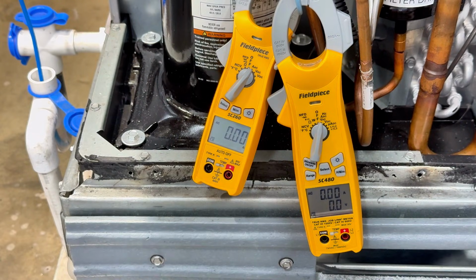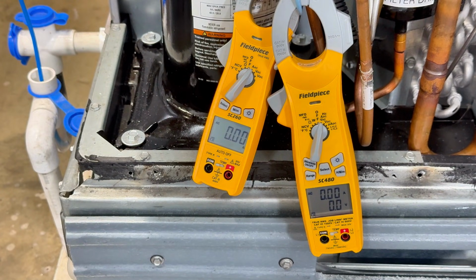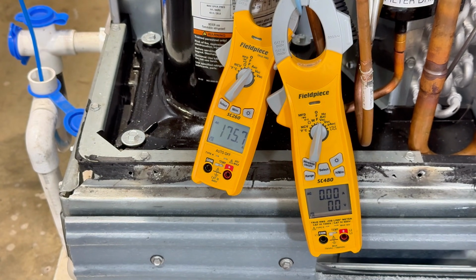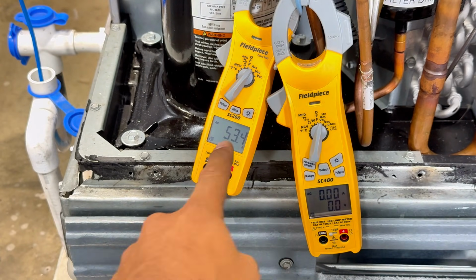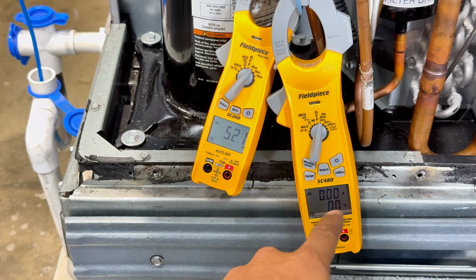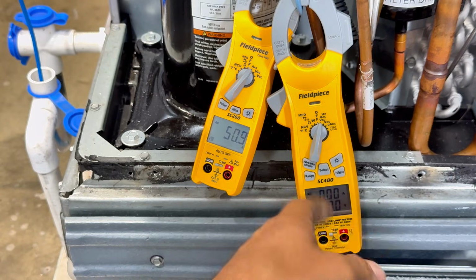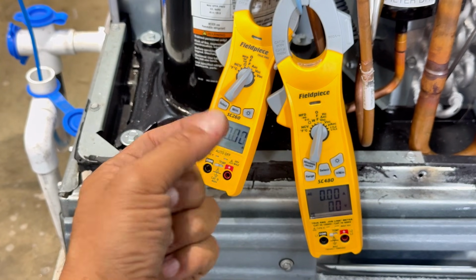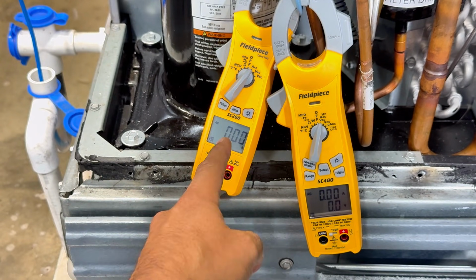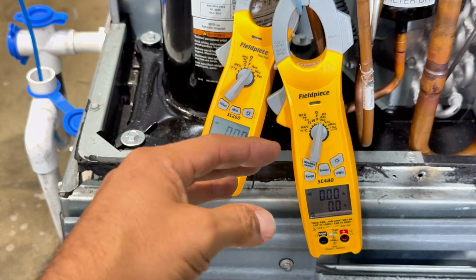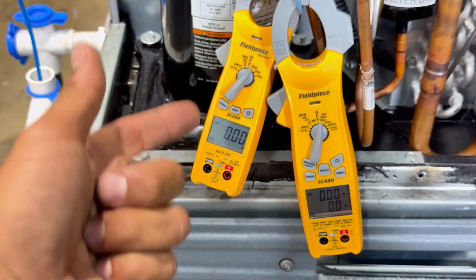I'm going to connect it. You see, 54. There's nothing going on with the start winding because I removed the Herm wire. And now it went off on the thermal overload. But you saw how much it was pulling? 51, 53, close to that 59.5.